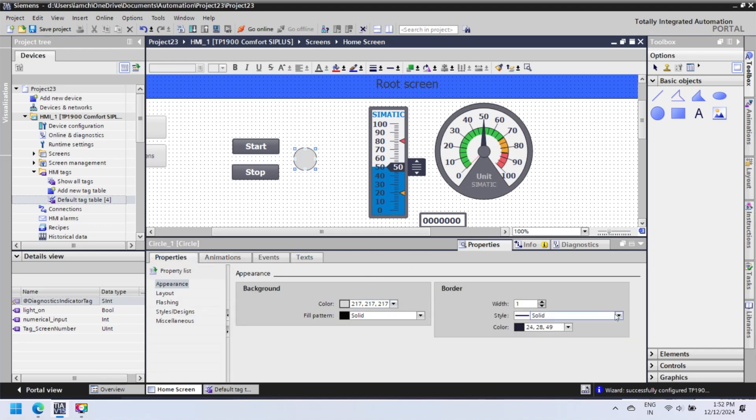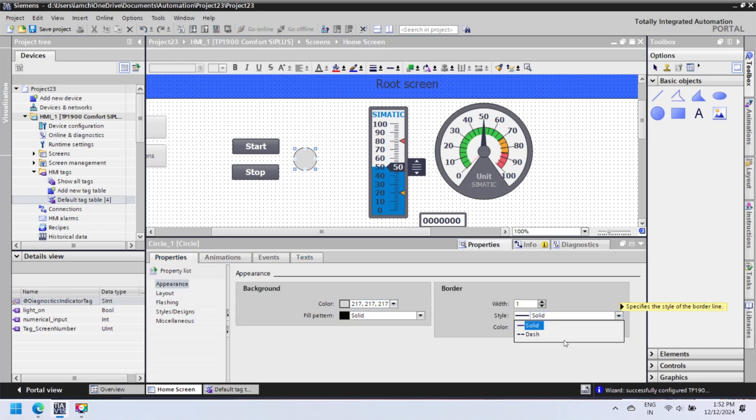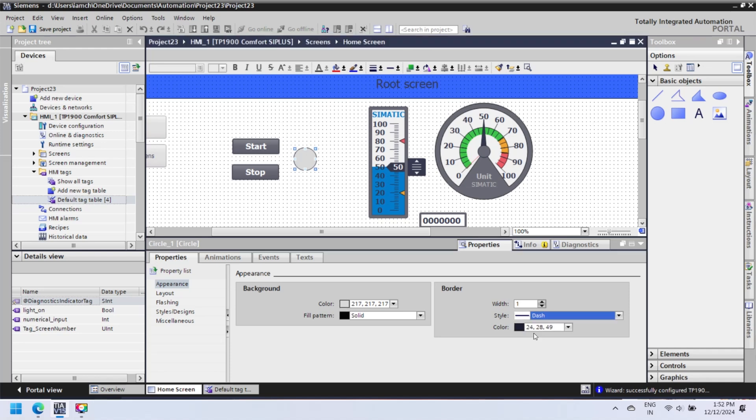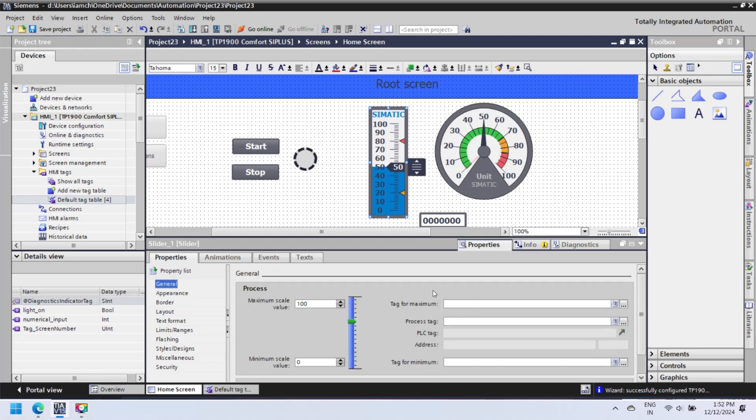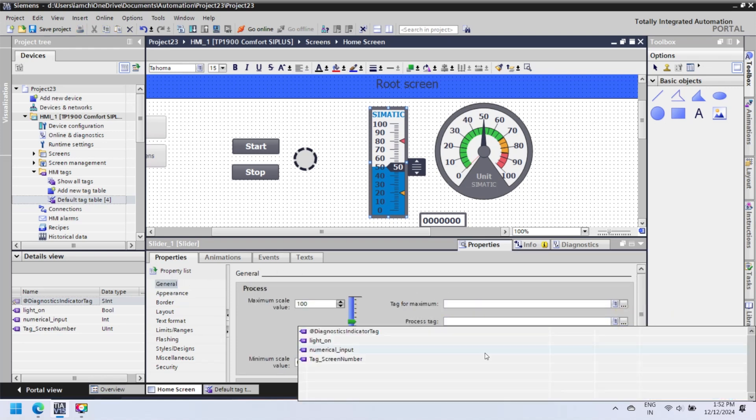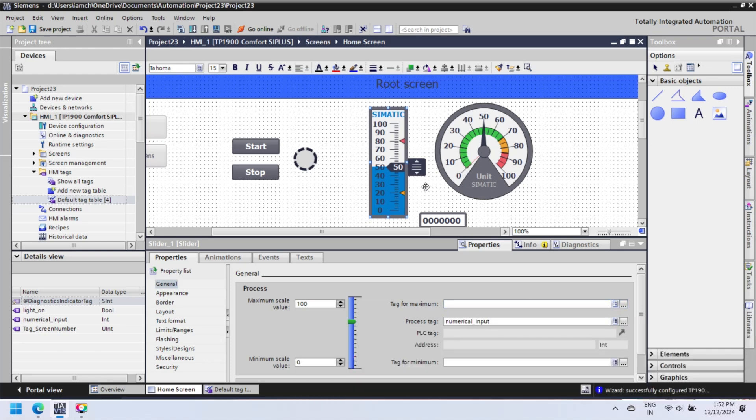Slider, gauge, and numerical input-output depend on numerical value, so we add a numerical_input tag for all three components as int. In property, define process tag for slider and gauge. Process tag: browse tag from tag table and then select to add.